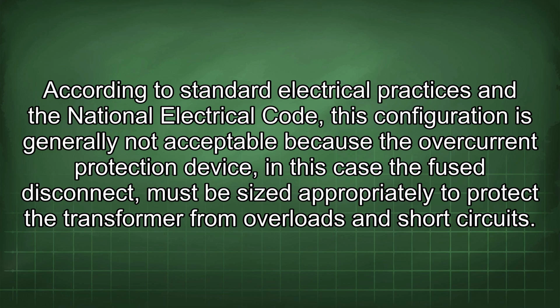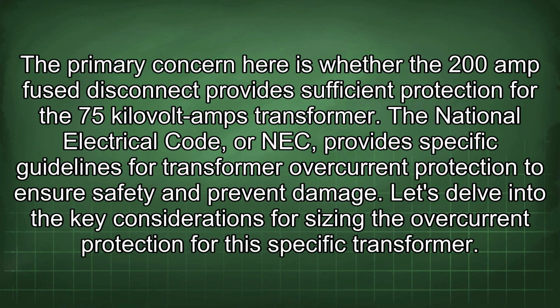device, in this case the fused disconnect, must be sized appropriately to protect the transformer from overloads and short circuits. The primary concern here is whether the 200 amp fused disconnect provides sufficient protection for the 75 kVA transformer. The National Electrical Code, or NEC, provides specific guidelines for transformer overcurrent protection to ensure safety and prevent damage. Let's delve into the key considerations for sizing the overcurrent protection for this specific transformer.